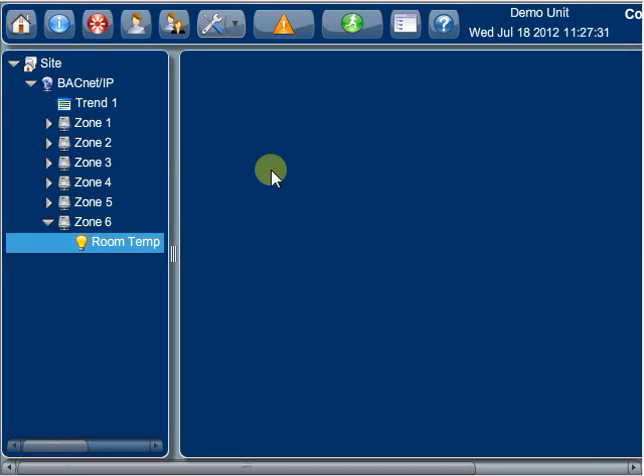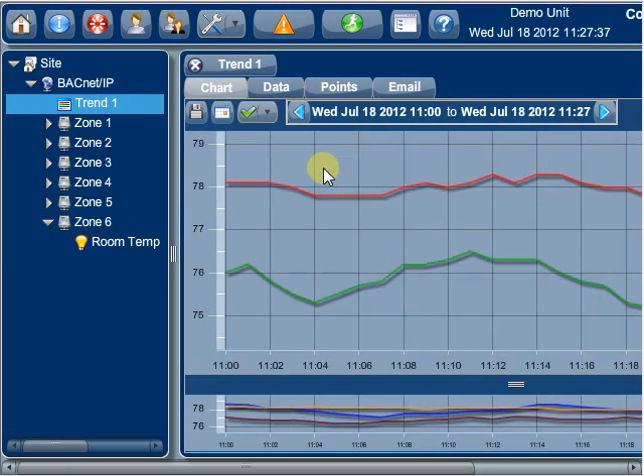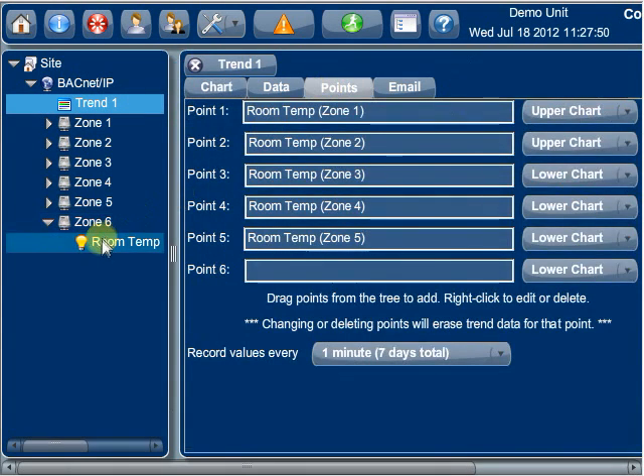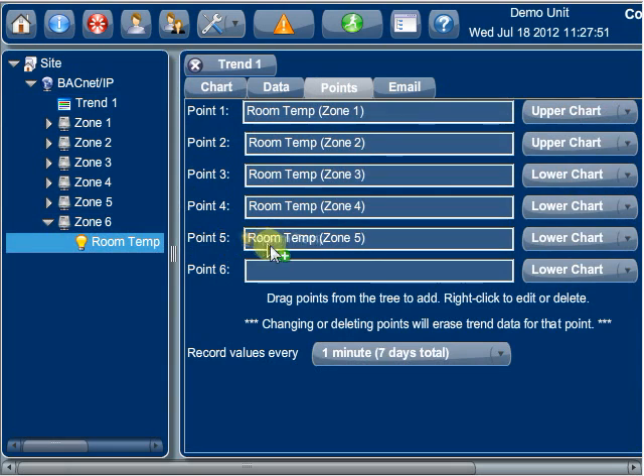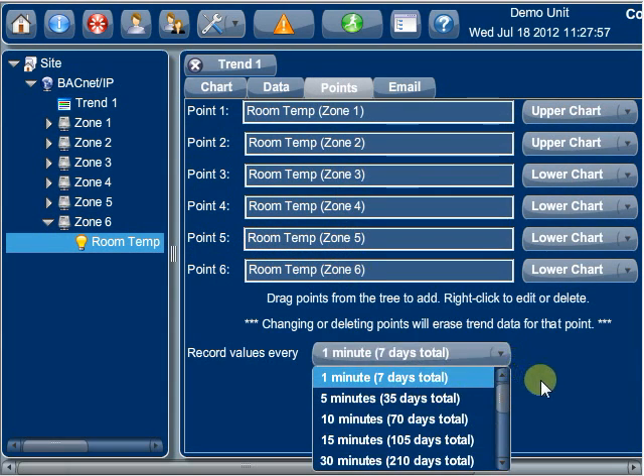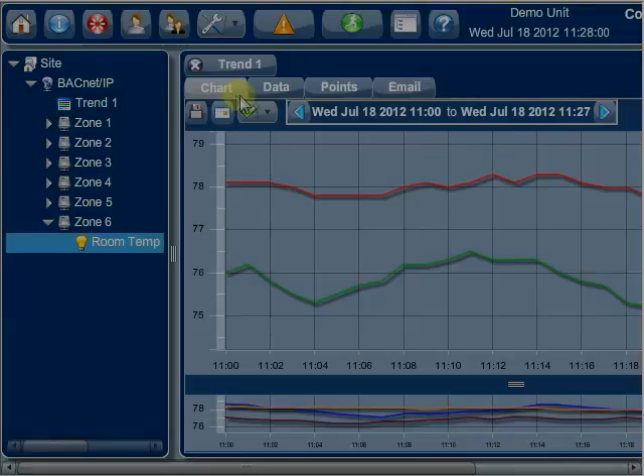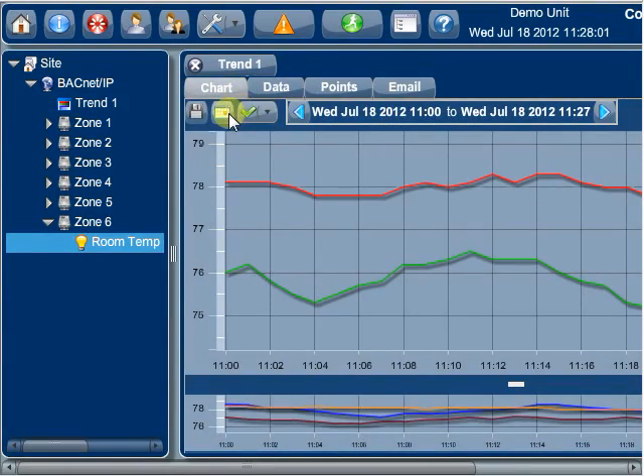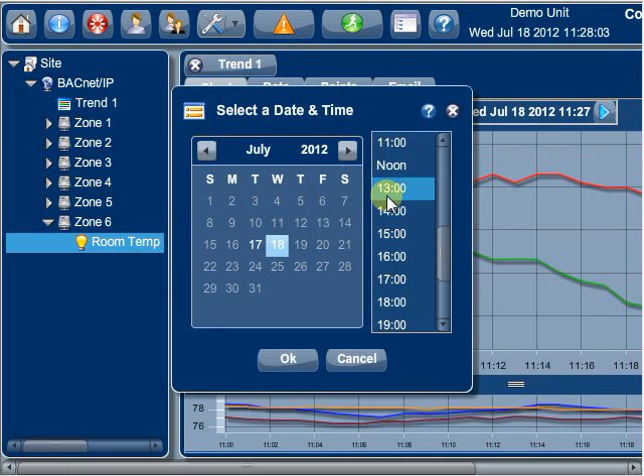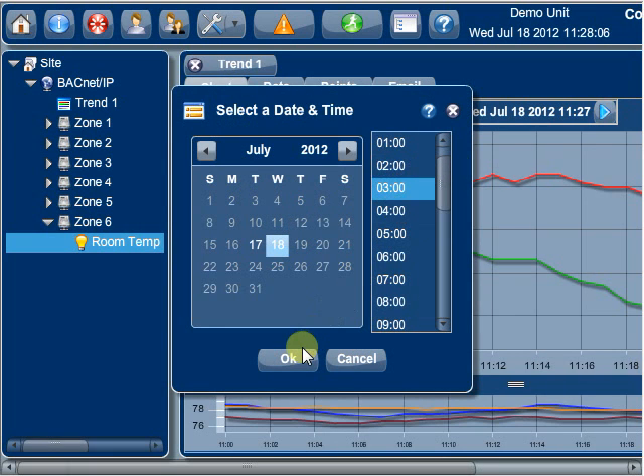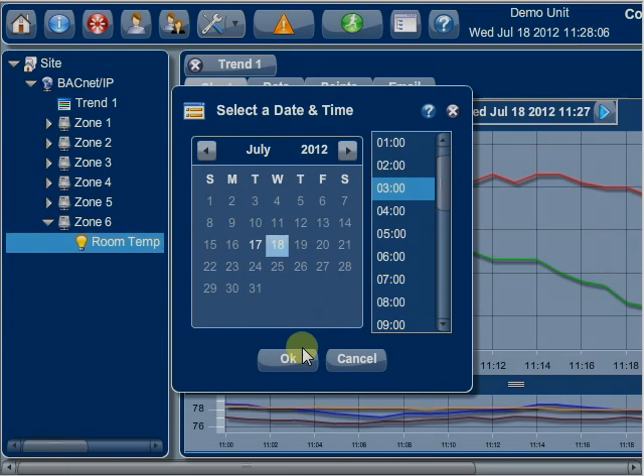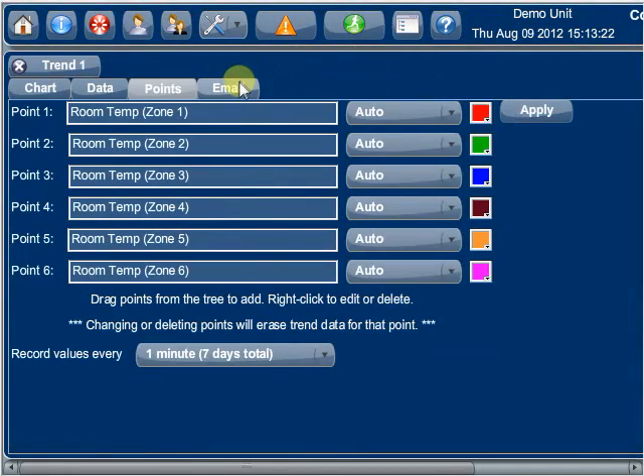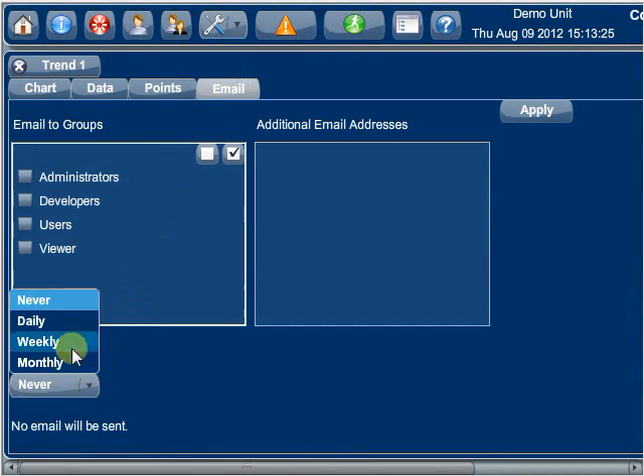Trends automatically record point values at specified intervals of time to allow for later viewing. Up to 6 points may be specified for a trend. Both a graphical line chart and a tabular text view are available per trend. A pop-up calendar makes it easy to choose the date and time. Multiple trends are supported and trends can be sent by email to different subscribers.